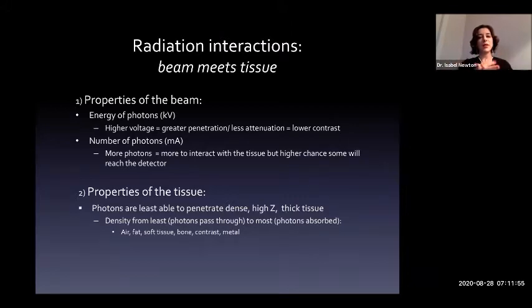So this is an important concept, because our fluoroscopy machines use an automatic exposure control, which averages over the tissues we're looking at, and says either give me more photons or I've had enough. And it modulates how many photons are driven through, and sometimes the energy.